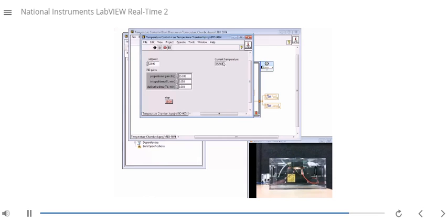The idea of the PID algorithm is that once we reach a steady state, we can maintain that state and apply whatever corrective adjustments are necessary to the system to keep us at that desired set point. And here we had a little bit of overshoot as it went a little bit too far. And now this integral component is helping us out and bringing us back up. Okay, so we're starting to get a little closer and it's going to settle much better over time.